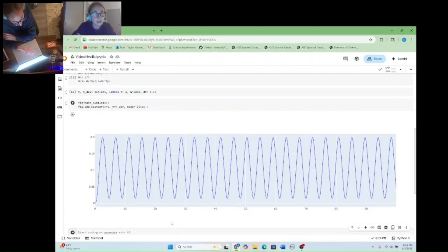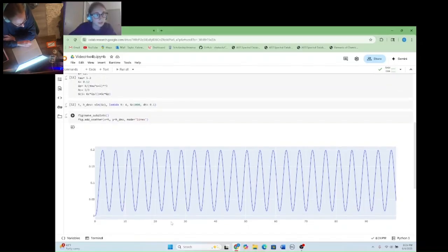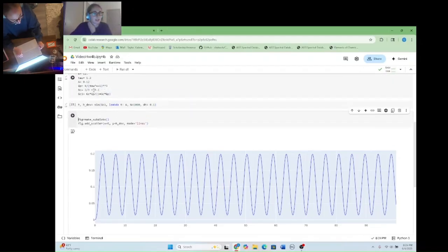So right here we see there's consistent peaks and valleys. It's not getting higher or lower, so this means that it's stable. So we have a stable Kc. So we're at the maximum stable Kc. So let's increase it to see what instability looks like for this, right? So let's do 1 point. And then let's look at our graph.